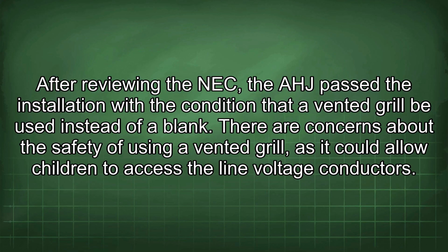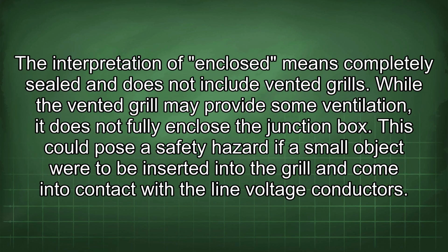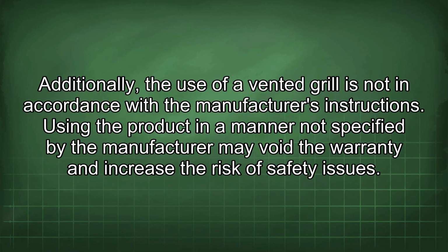There are concerns about the safety of using a vented grill, as it could allow children to access the line voltage conductors. The interpretation of enclosed means completely sealed and does not include vented grills. While the vented grill may provide some ventilation, it does not fully enclose the junction box. This could pose a safety hazard if a small object were to be inserted into the grill and come into contact with the line voltage conductors. Additionally, the use of a vented grill is not in accordance with the manufacturer's instructions. Using the product in a manner not specified by the manufacturer may void the warranty and increase the risk of safety issues.